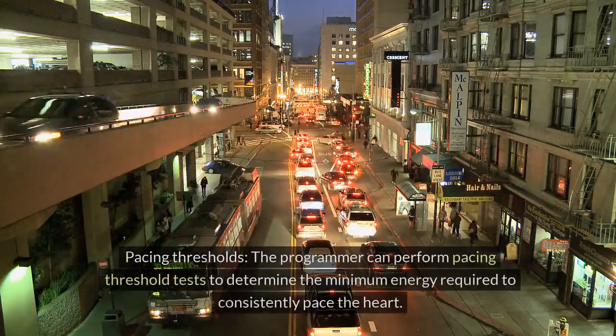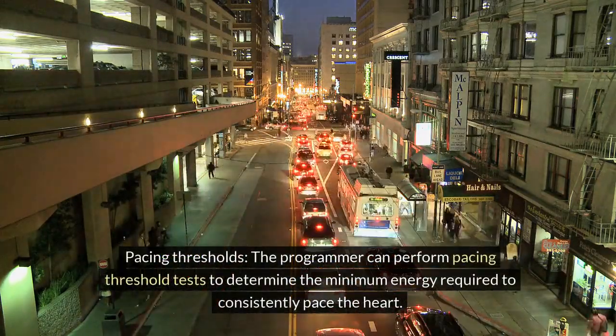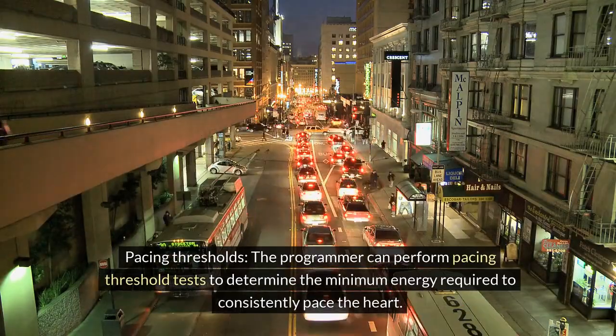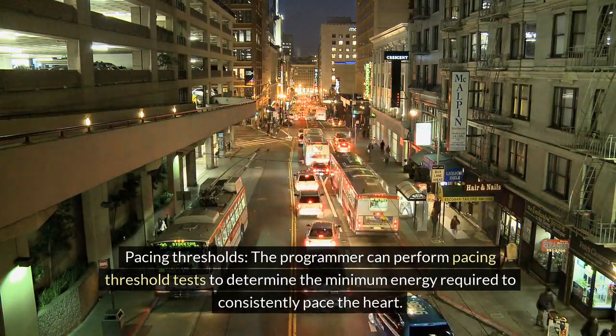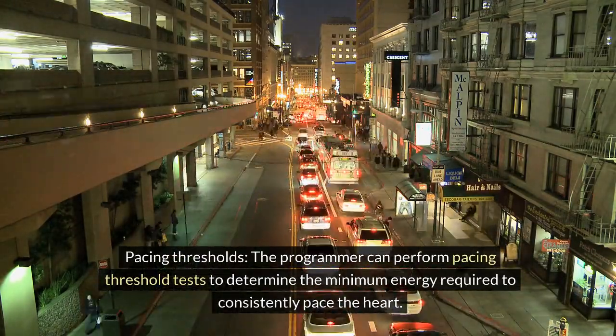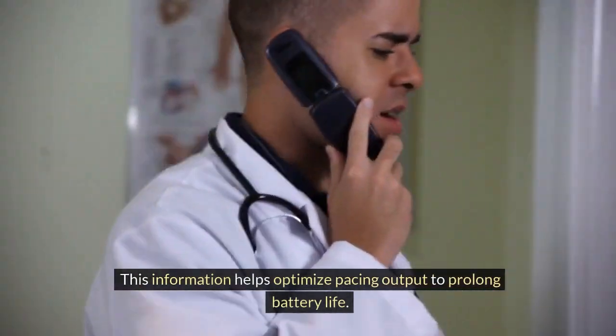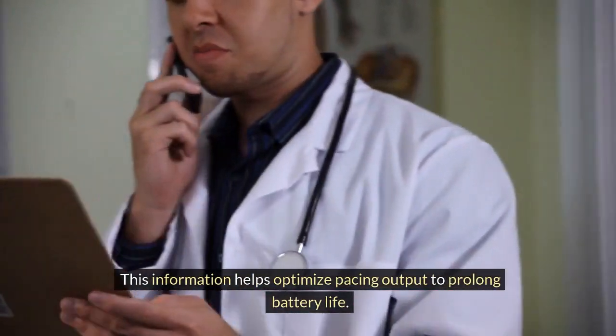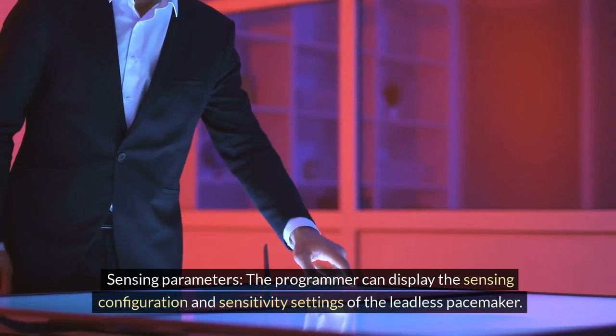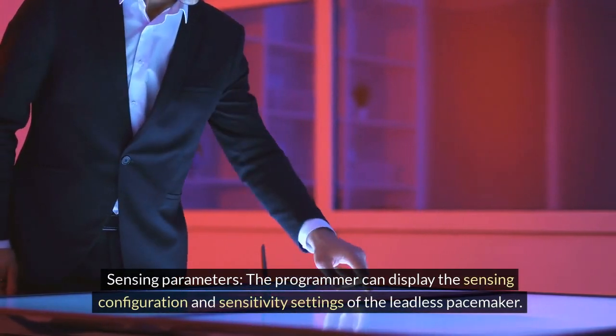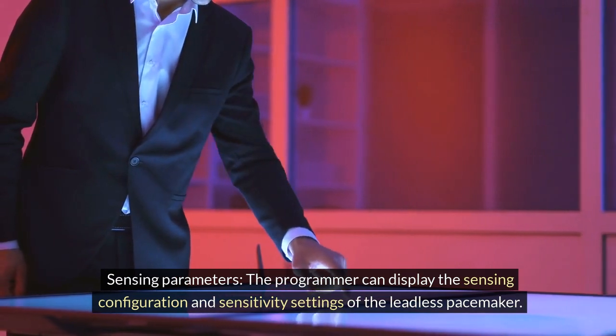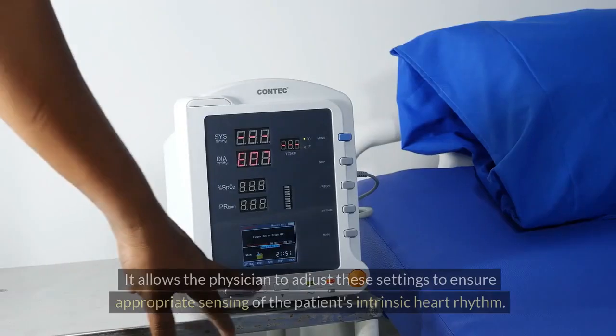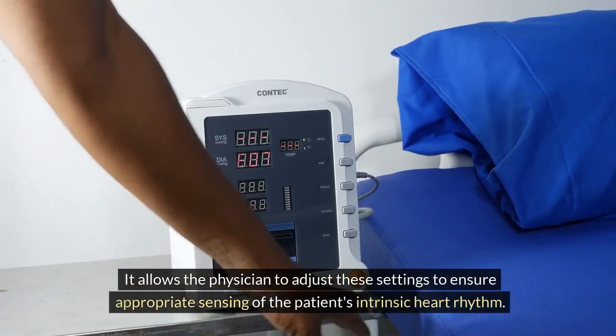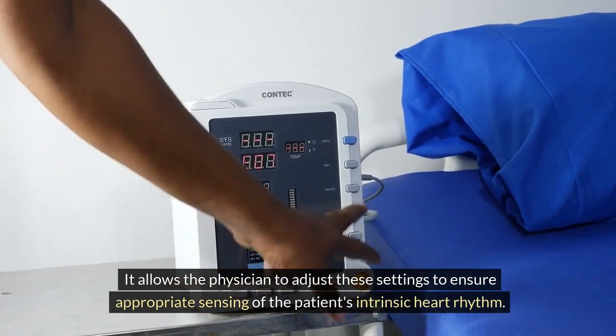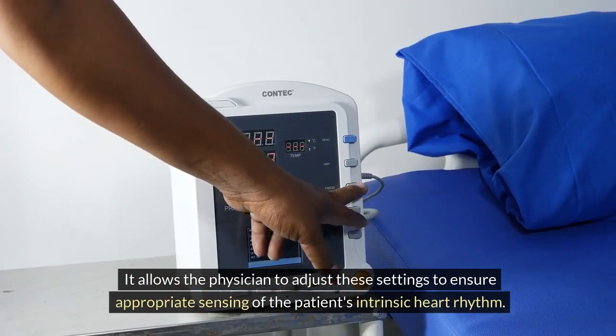4. Pacing thresholds. The programmer can perform pacing threshold tests to determine the minimum energy required to consistently pace the heart. This information helps optimize pacing output to prolong battery life. 5. Sensing parameters. The programmer can display the sensing configuration and sensitivity settings of the leadless pacemaker. It allows the physician to adjust these settings to ensure appropriate sensing of the patient's intrinsic heart rhythm.